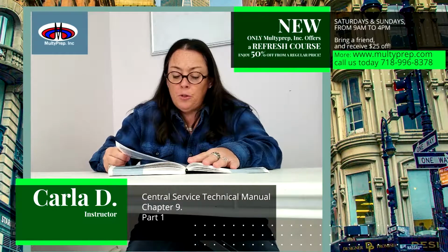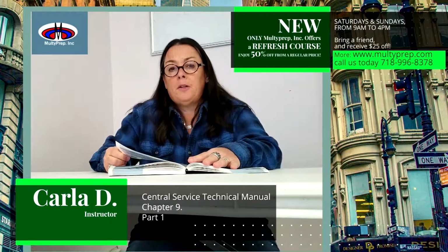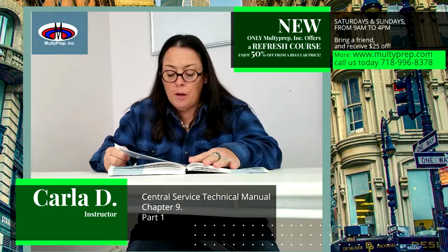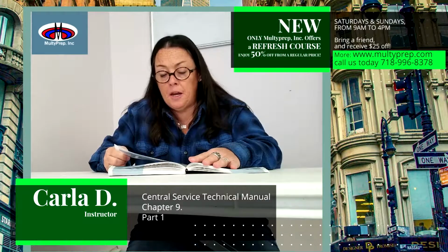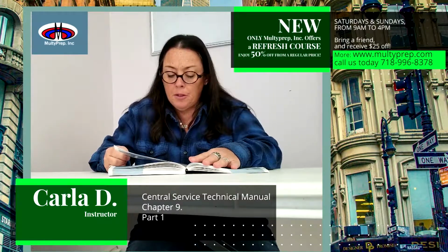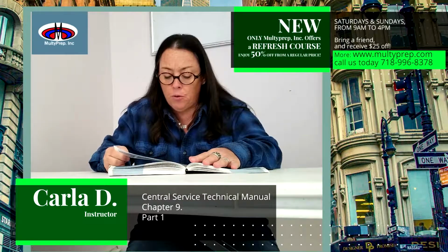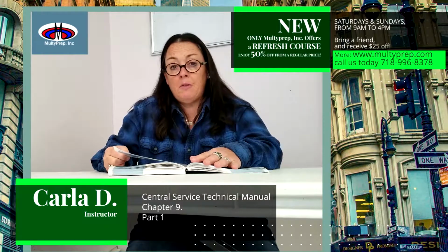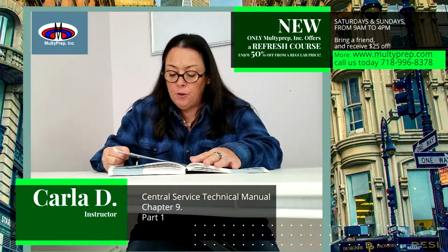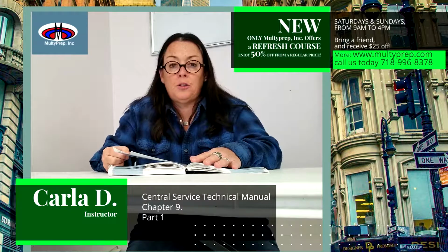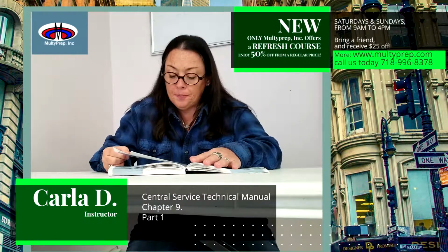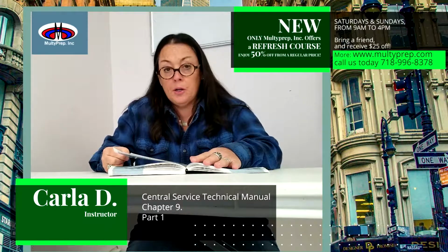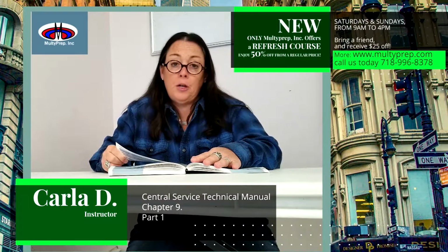Glutaraldehyde-based products can be used in automated or manual high-level disinfectant processes. Most glutaraldehyde-based instrument disinfectants are labeled for reuse for 14 to 28 days. During the recommended reuse period, the concentration of glutaraldehyde in the solution should be tested with test strips recommended by the manufacturer. If it falls below its minimum effective concentration, MEC, it should be discarded, regardless of how many days the solution has been in use.